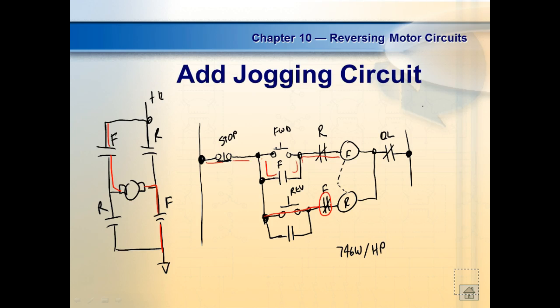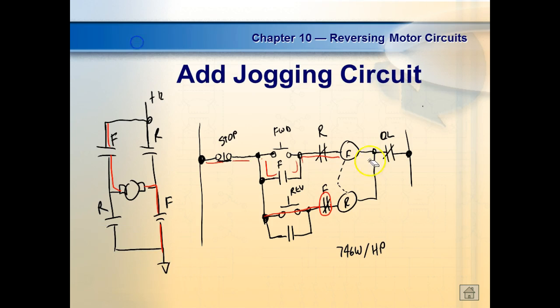So the way we're going to have to wire ours up, since we don't have a true reverser, is we don't have this. What we have is we're going to have this, and the corrections in the lab book. I've got to get a reverse contact right here. So what numbers would I use? I don't have it here. So here, this is my overload. That right there would be 9. That would be 9 on the other one. This would be 10. This is going to be 10.